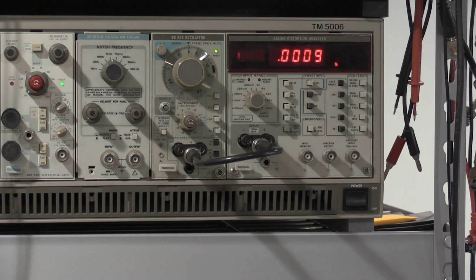This is also measuring a lot more of the harmonic content than the spectrum analyzer would, where the spectrum analyzer and the worksheet test up to the 5th harmonic. The AA501 is looking at stuff out to 300 kilohertz. So that's why the numbers can be slightly askew. But this particular SG505 is working quite well and should be good to go for some projects here in the lab.